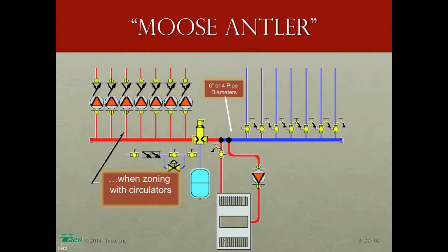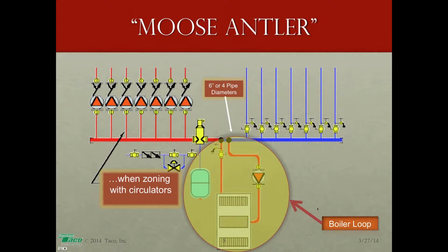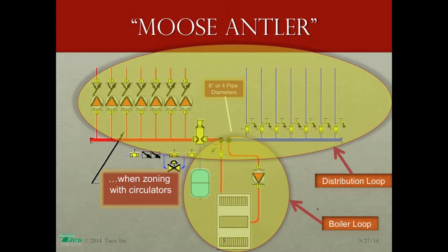But the bigger section is the distribution section. Some people have called that the primary part. I prefer to just be descriptive rather than talking primary, secondary. Just show what they are. I call it the boiler loop. That's pretty straightforward. That's the pipe that's going in and out of the boiler and connecting to your header. And then there is the distribution loop. That's the distribution side of the system.